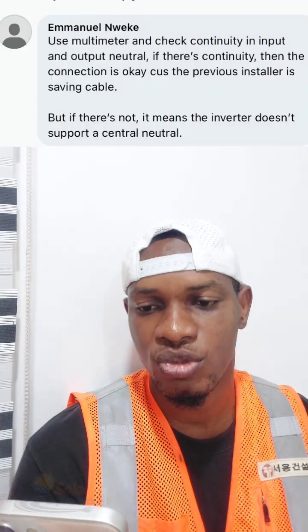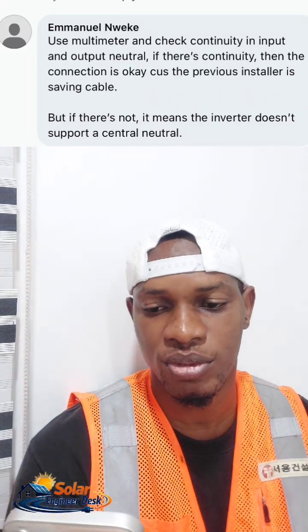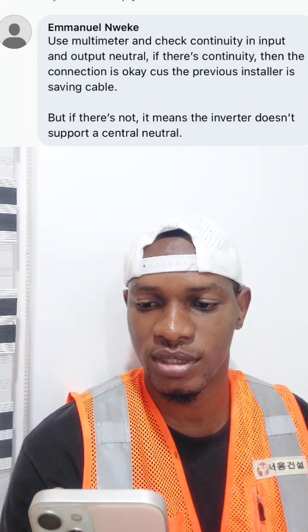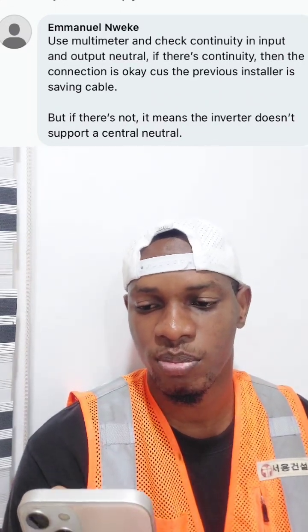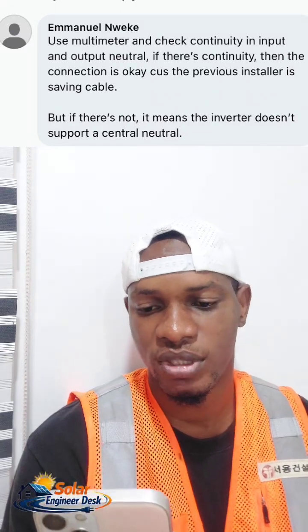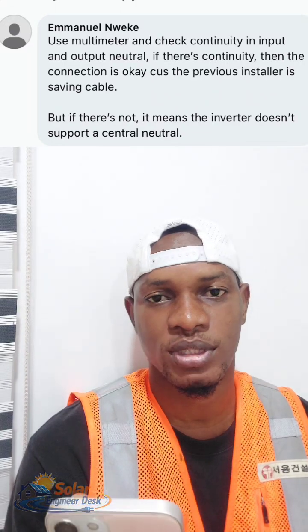Emmanuel Wike said, use a multimeter and check continuity in input and output neutral. If there's continuity, then the connection is okay because the previous installer was saving cable. But if there is not, it means the inverter doesn't support a central neutral. Just like I said earlier, most times when I go for installations like that and it's an inverter I've not used before, I test the neutral first. On your multimeter, just set it to continuity, put both your negative and positive probes on the two neutrals and test. If it makes that beep sound, it means it is interconnected, so you can use one cable. If it is not interconnected, you have to run the cable separately.